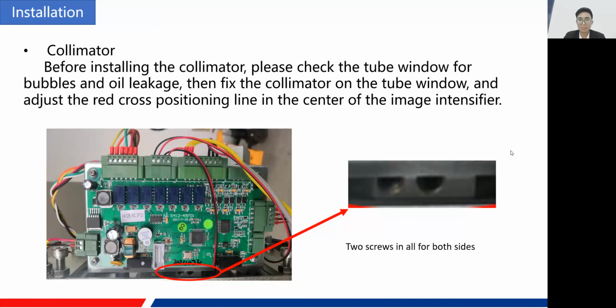And also comes the collimator. It was uninstalled, and you also need to install it. Before the installation of the collimator, first you need to check the tube, the X-ray assembly tube. You need to check its window to see if there are any bubbles or oil leakage, and make sure it works fine. And if anything is abnormal, please give feedback in a timely manner.